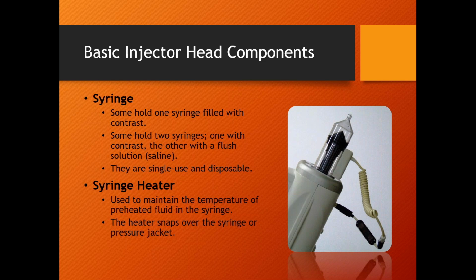Yep, I talked about that. And I mentioned the syringe heater down at the bottom, used to maintain the temperature of the contrast. Now, if I have 2 syringes here, the green side here, this is contrast, the blue side, blue is water, so this is the saline. Saline is basically salt water. So if I have a heater, the whole purpose of the heater is to keep my syrupy contrast at 37 degrees Celsius. So if we're doing a dual shot where we're going to fire some contrast in the patient and saline as well, we also have to keep the saline at 37 degrees Celsius.